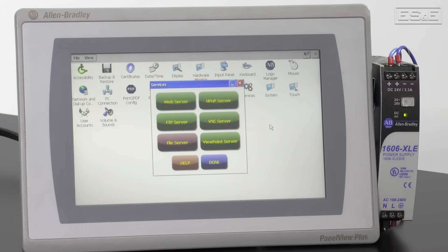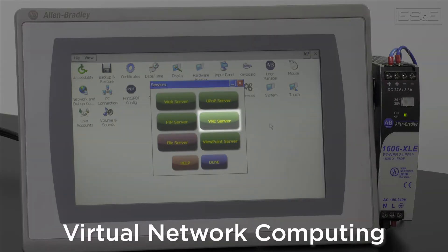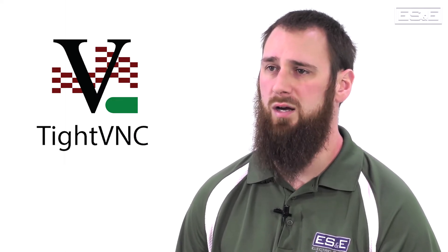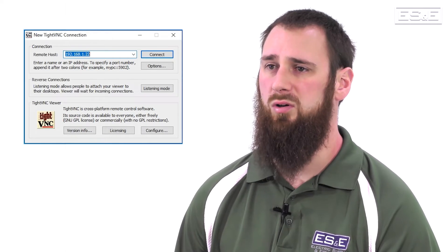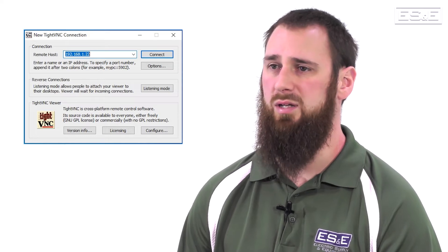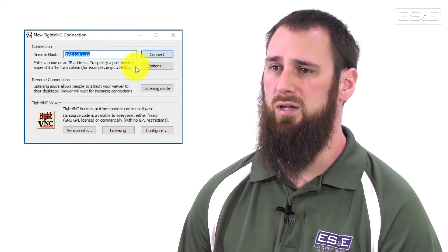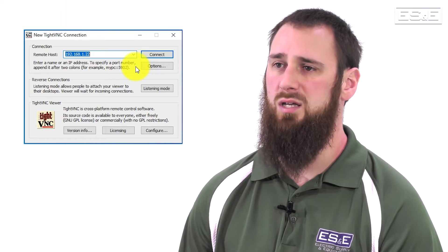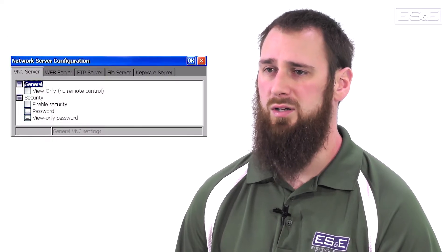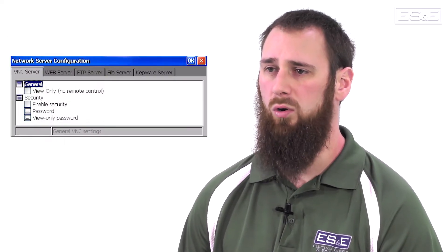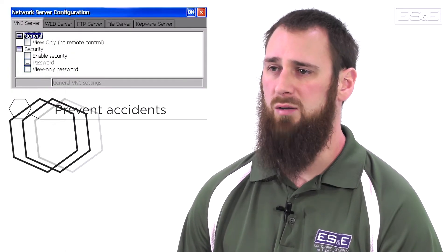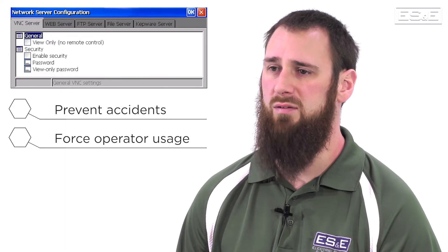The next server that is useful is the VNC server, or Virtual Network Computing. The VNC server requires you to install a VNC viewer software on your PC, but allows you to take control of the PanelView remotely. All Rockwell PanelViews have this capability. It is a very convenient feature when it comes to diagnostics or seeing what the actual operator sees without being in front of the equipment. You can configure the server to allow remote control or view only capabilities, which could prevent accidental button clicks remotely and will force the operator to do the navigation and input.